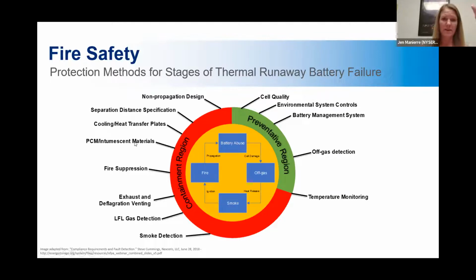And beyond that, say a fire does occur, there are other safety features in place to make sure that that fire in one section of a battery energy storage system does not transfer itself to other parts of the battery energy storage system. Like dissipating any heat that does build up, or specifying the separation distance that needs to be between different blocks of batteries, or even different containers of batteries. For example, the fire code specifies how far apart they need to be so that if there happens to be a fire in one, it's at least not going to spread to the other, and it's going to be contained within itself. And that's what, at the very top here, back to the 12 o'clock mark again, non-propagation design. So trying to keep everything that could go wrong, if it does go wrong, to a minimum, and not let it go beyond itself.